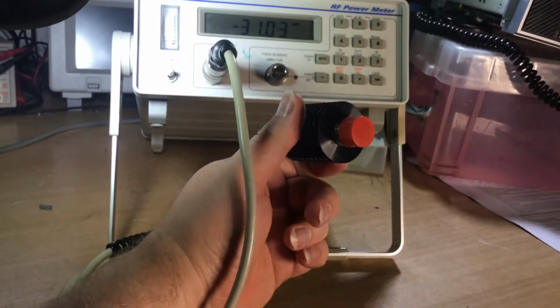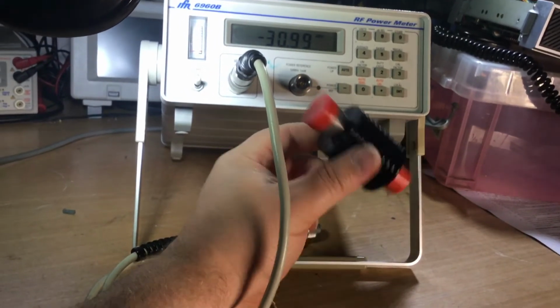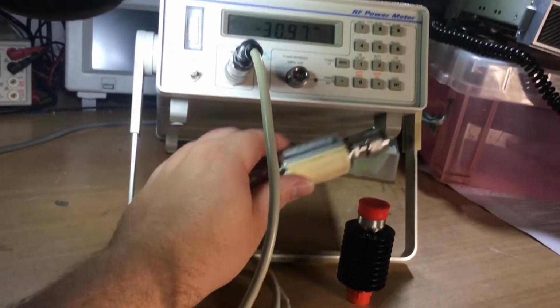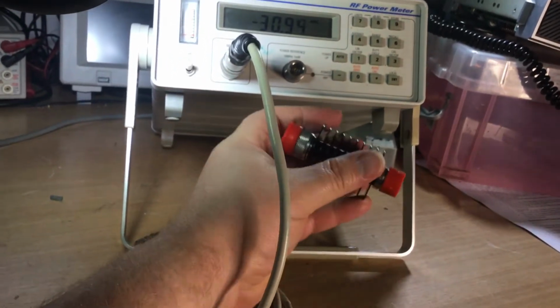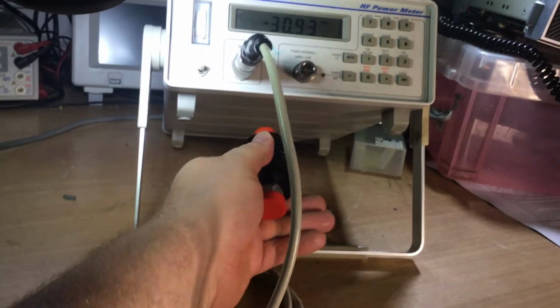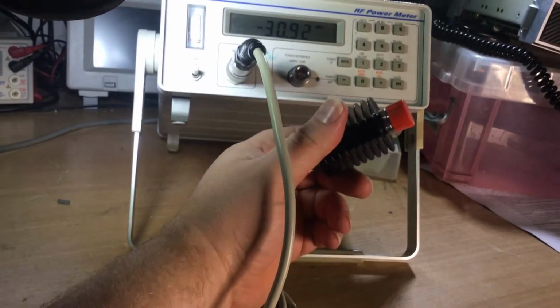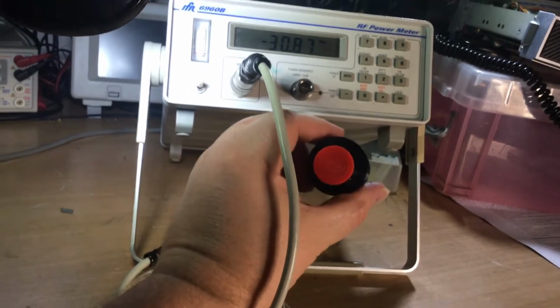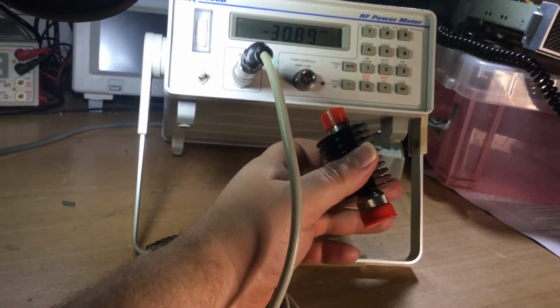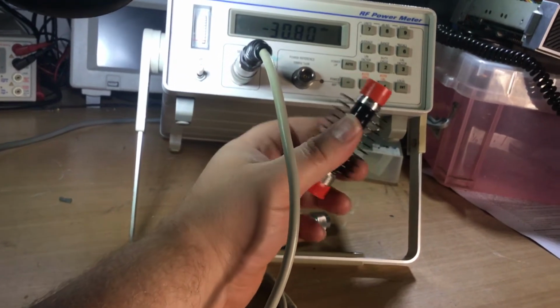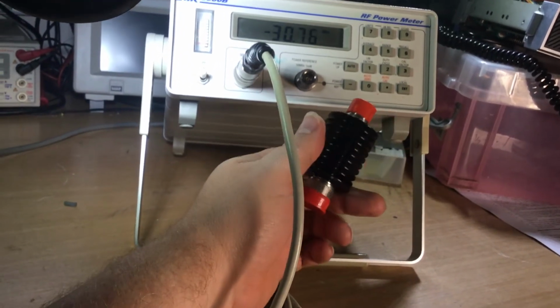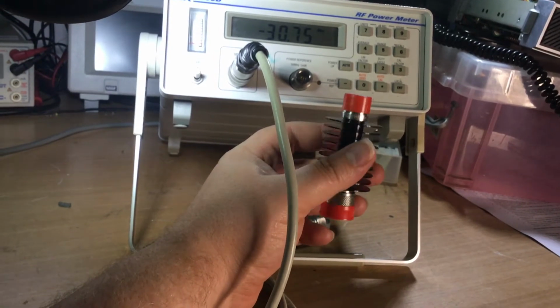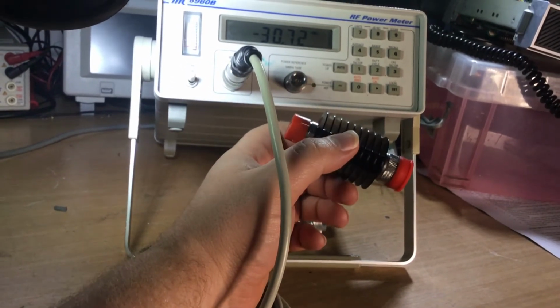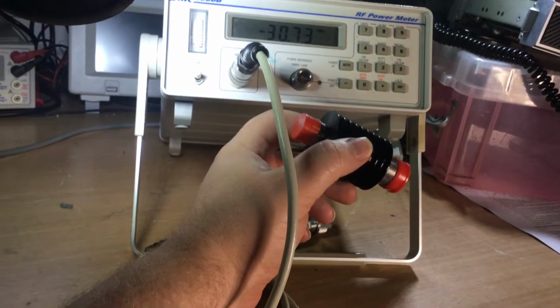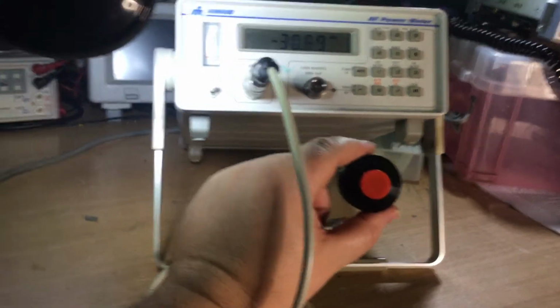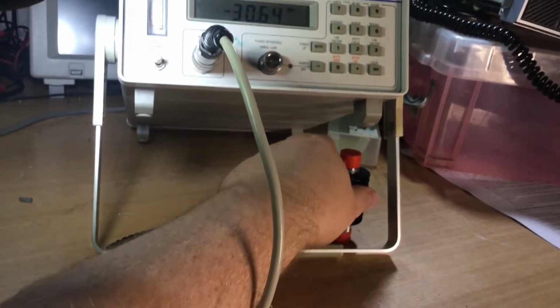This particular RF attenuator goes up to 4.5 gigahertz, which aligns with what this sensor can measure, but I wouldn't use that with a 20 gigahertz signal, because obviously if I'm using a 20 gigahertz sensor, you'd want an attenuator that can handle up to 20 gigahertz as well. So this is where calibration can go out the window a little bit if you're using attenuators that are cheap, that are not precise attenuation factors, or that are not capable of attenuating at the frequencies you're using them at. So you've got to be very careful with that and make sure you use the right attenuators with the right sensors.